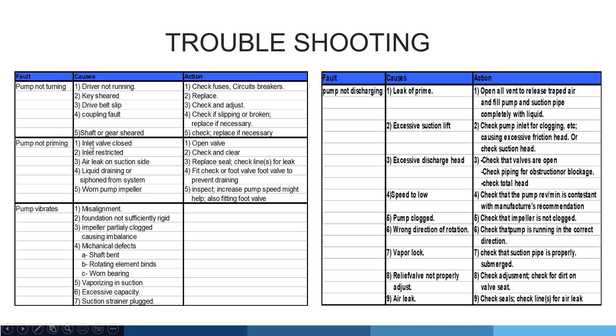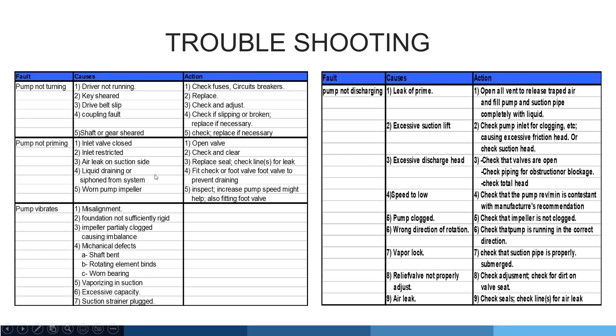Pump not priming. First check the inlet valve — if it is closed, open it. If the inlet is restricted or clogged with debris, check and clear it. If there is air leakage on the suction side, replace the seal, check the line, bore with water, and remove the air from the suction side. If liquid is draining or siphoning from the system, check the foot valve. In case of leakage, correct the foot valve with a gasket, fill with water, then start the pump. Also inspect the impeller and consider increasing pump speed. Most of the time the foot valve and air lock are the main causes, so check these two things before attempting major repairs.